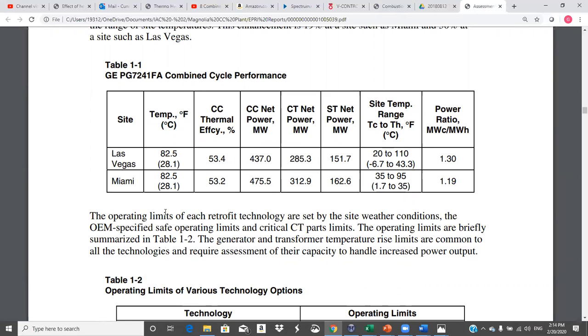So here's combined cycle performance based on locations. This is kind of interesting. What's going to be so different between Las Vegas and Miami? Maybe the humidity? Yeah. One of the big impacts is that when you don't have humidity, the evaporative coolers work a whole lot better because you can evaporate more and you get more temperature depression into your gas turbine cycle, and that ups your efficiency and your power out. So you can see efficiency is a little bit better. Net power, oh, it's more in Miami. Well, I'm not sure why that is. Huh. Maybe I should read the report. But anyway, that's what they're reporting here. Site temperature. I'm not sure if this is average or if this is at this temperature. Interesting.